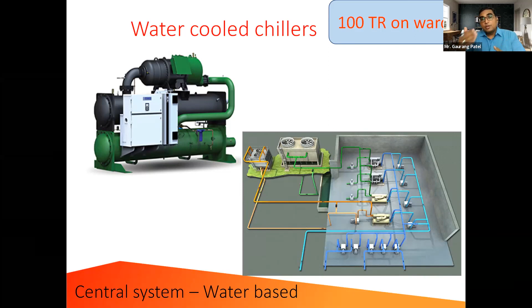Now that particular process is governed by the wet bulb temperature, and the wet bulb temperature is always lower than the dry bulb temperature. So that also increases the efficiency of water cooled chillers, and hence they are selected for applications where you have loads higher than 500 ton. They are available from 100 ton, but looking at the complexity of the designs and operations, they are selected for applications where the load is above 400 to 500 tons. So for big applications like a big mall in Ahmedabad, or Hyatt hotels, any big hotels of similar nature, they all work on water cooled chillers.